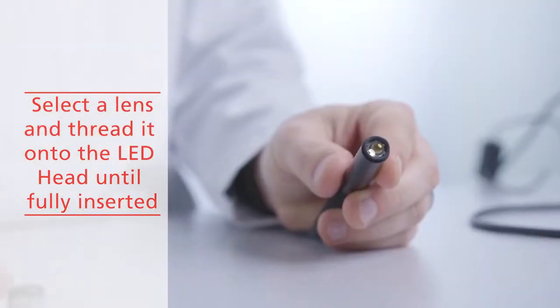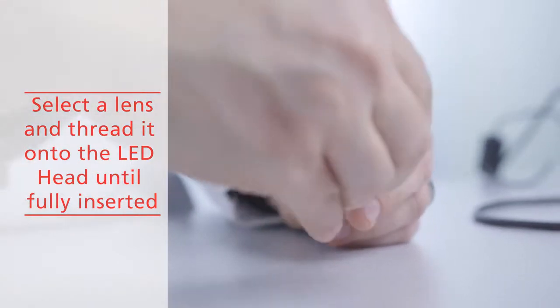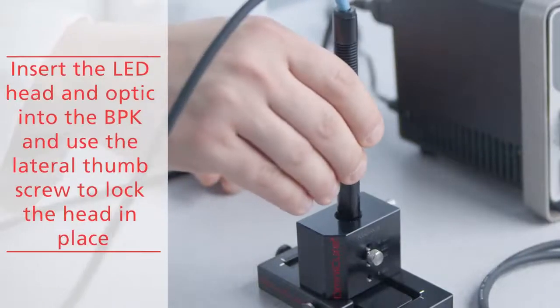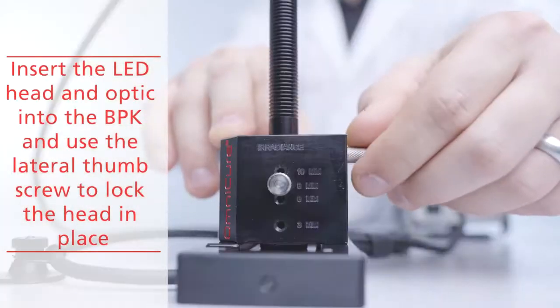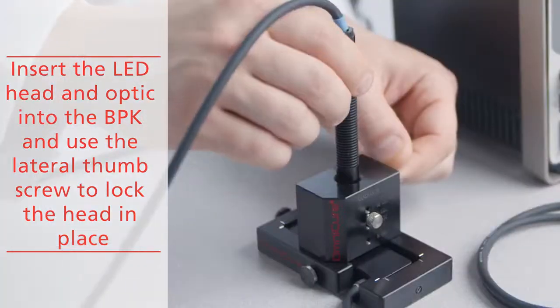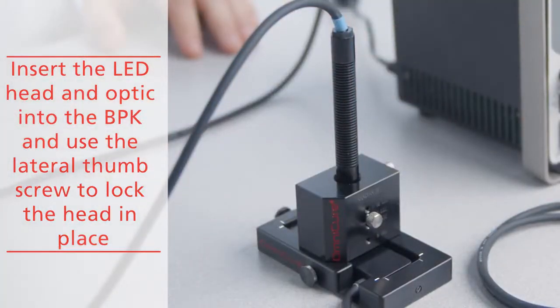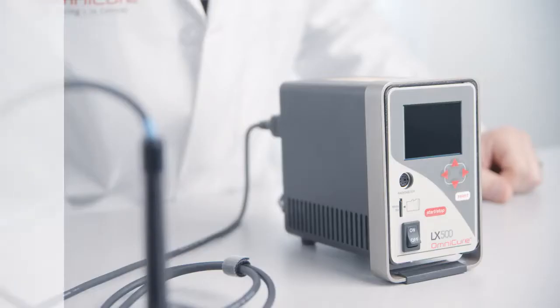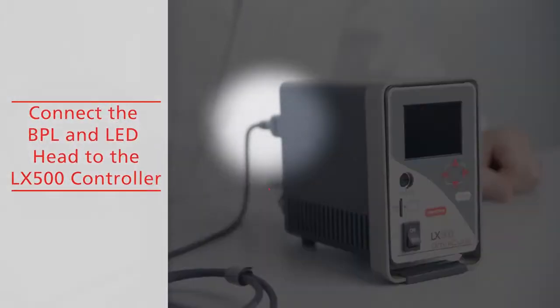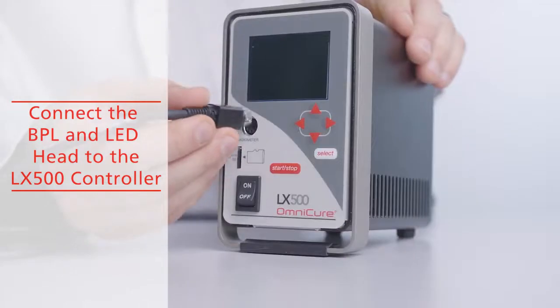Note that the lens needs to be absolutely clean to achieve accurate measurements. Dust, dirt, residue, or fingerprints can all affect the measured value significantly. Insert the LED head and optic into the pre-configured beam positioning kit and use the lateral thumb screw to lock the head in place. Once the setup is complete, the calibration kit and the LED head can be connected to the LX500 controller.